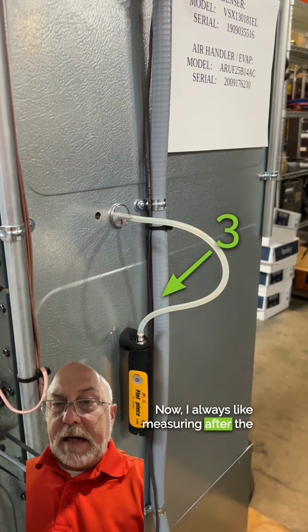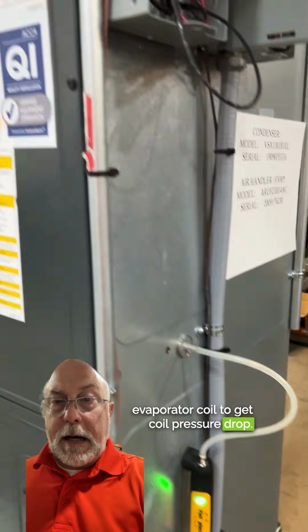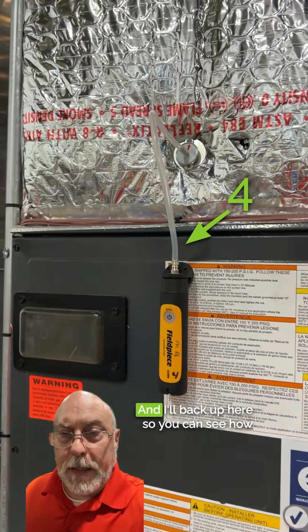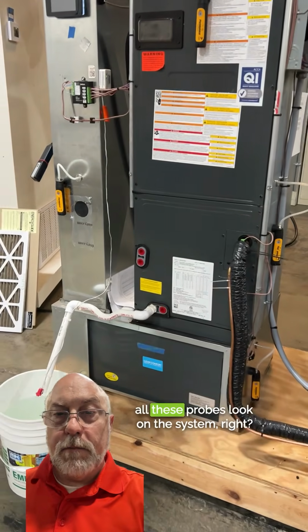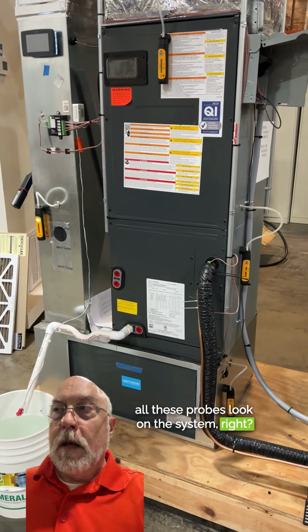Now, I always like measuring after the evaporator coil to get coil pressure drop. Then I've got one up here in the supply, and I'll back up here so you can see how all these probes look on the system, right? All right, so now let's go and take a look at the MeasureQuick application.